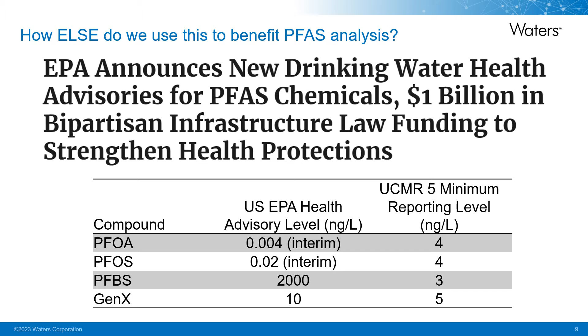The health advisory levels that were released by the EPA were in drinking water, and those types of samples require SPE sample preparation according to EPA methods. So we did the sample preparation using SPE at the appropriate levels for PFOA and PFOS and ran them on the TQ Absolute. The result of that analysis was that the TQ Absolute is not the limiting factor here. It actually has really good sensitivity to easily reach the appropriate levels needed for the interim values.